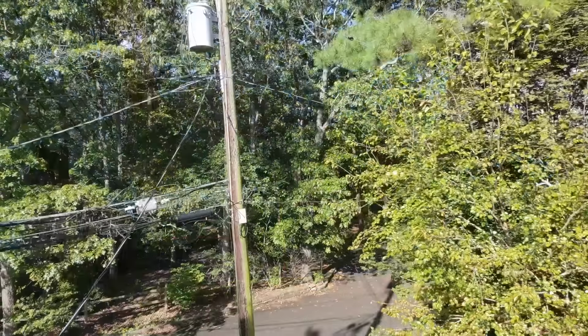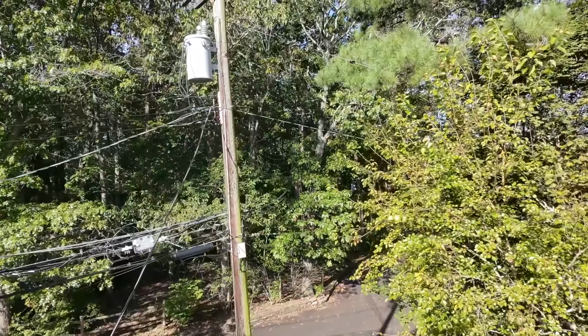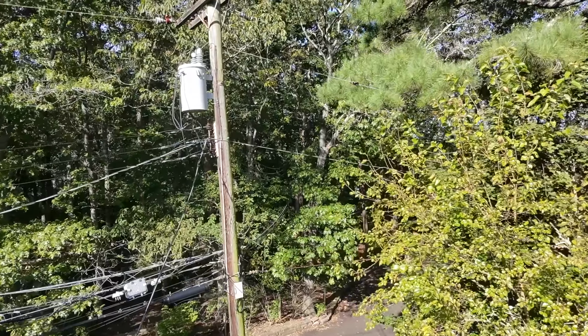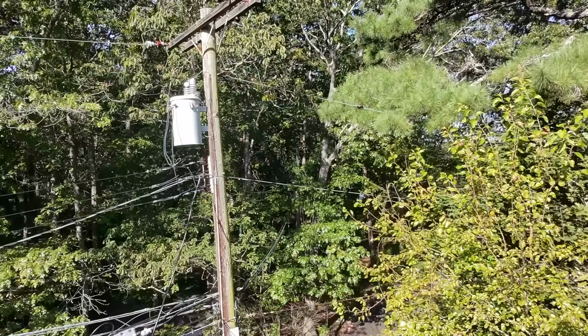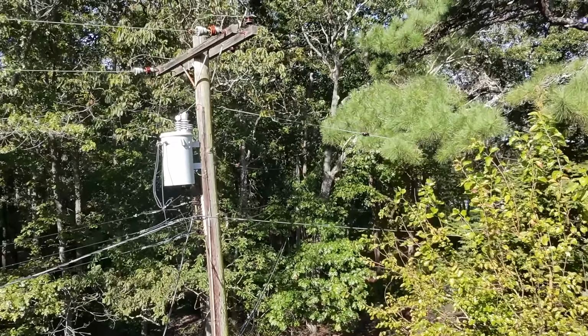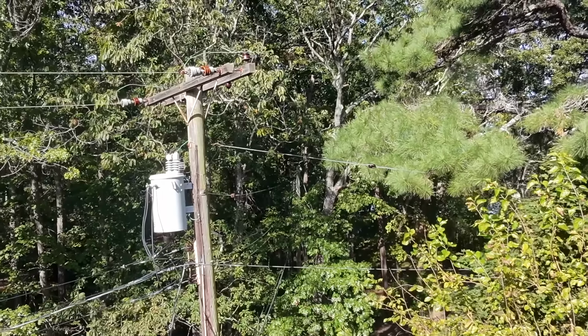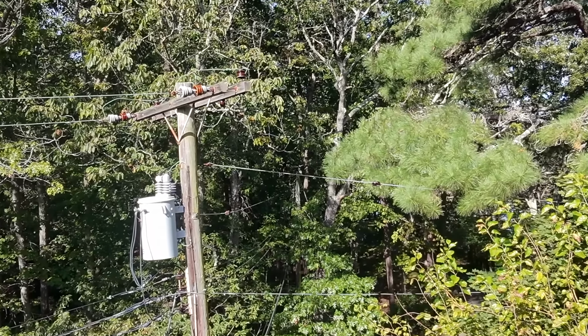Up on that pole right there, there's an impedance rating that gives us our interrupt amperage rating. And that interrupt amperage rating in most residential areas is 10,000 amps, or interrupt current is 10,000 amps. Why is this important? Because if we had a circuit breaker less than 10,000 available interrupt current amps, then what could happen is on a short circuit or a ground fault on the service equipment, that surge of current is going to go through that circuit breaker.